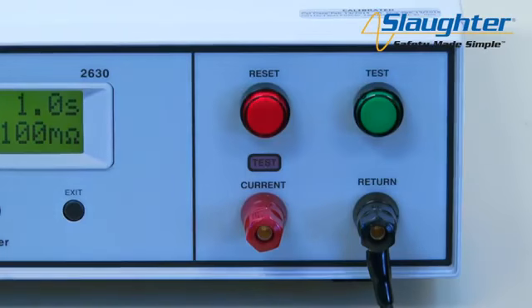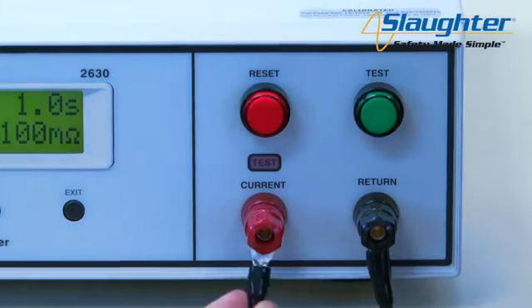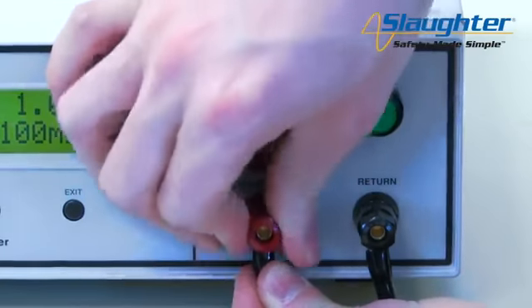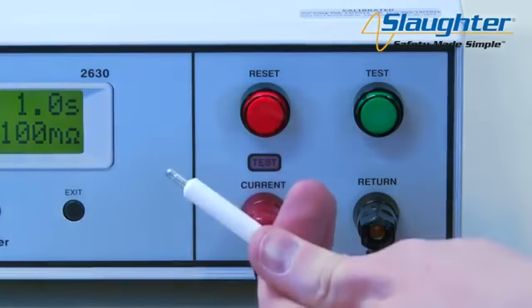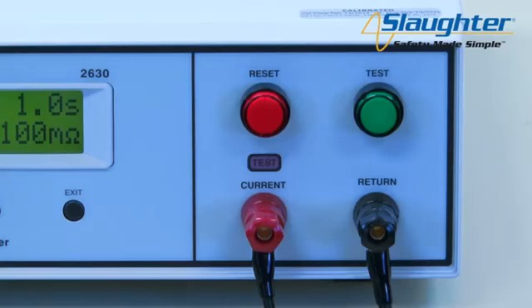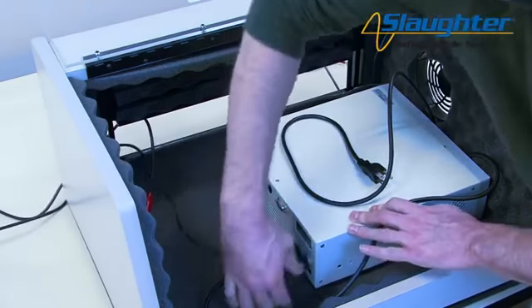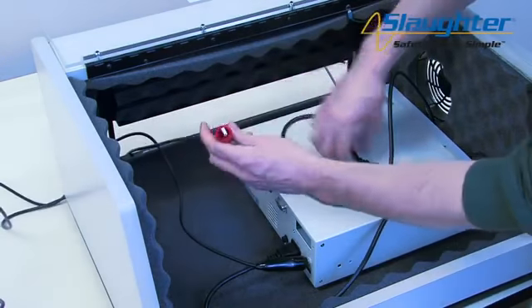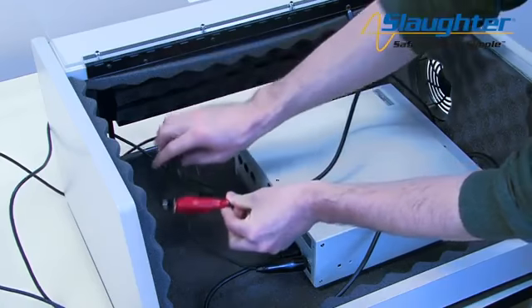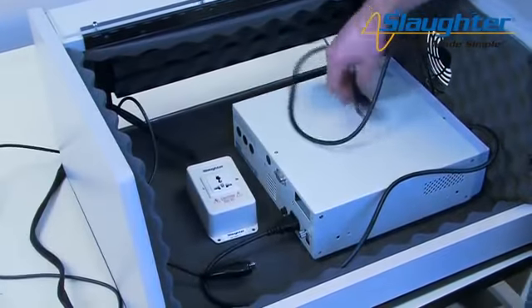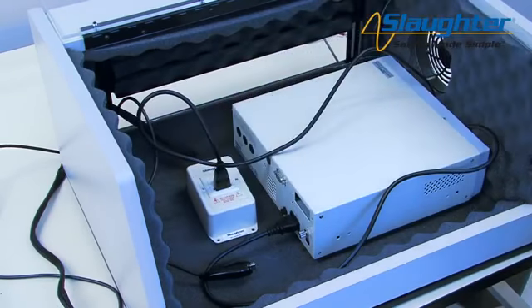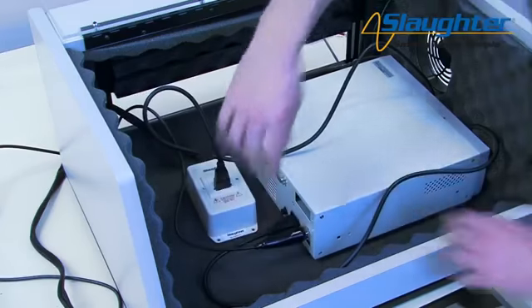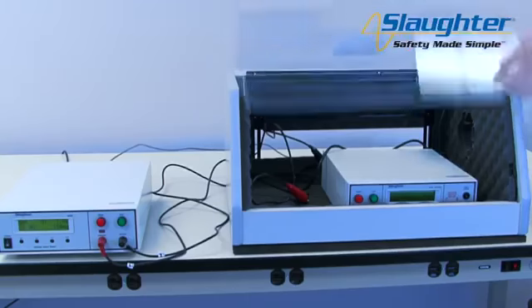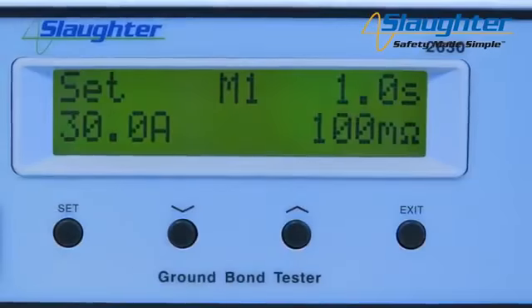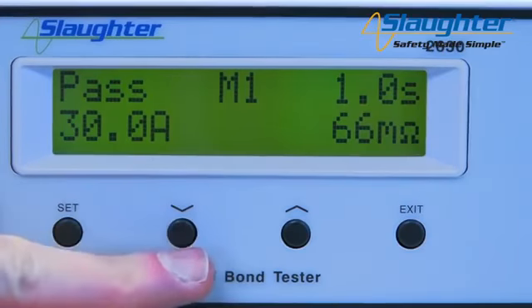If you're using the universal style adapter box instead of the clip leads, first connect the return clip lead to the return terminal. Then, connect the adapter box to the current terminal. You will not need to connect the white Alden style lead, as this is only used for high voltage testing. Connect the return lead to the chassis of the DUT. Finally, connect the high current lead to the ground wire. You are now ready to run your test sequence. If using the adapter box, simply plug the product's 3-pronged line cord into the adapter box and connect the return lead to the chassis of the DUT. Close the DUT enclosure door, stand back, and push the Test button to run your test sequence. Once your test sequence has completed, press the up and down arrow keys to review your results.